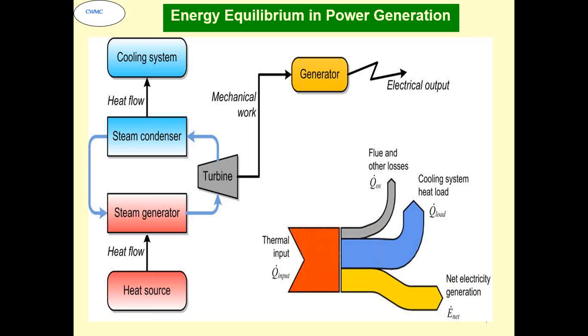If you look at the general efficiency, the total thermal input is something which is in the red color that you see. And then in the yellow color, what you see is the net electricity generation out of that. Blue color is the heat losses on account of the cooling water system. And then the gray color is the other losses in terms of the boiler flue gases and other things.